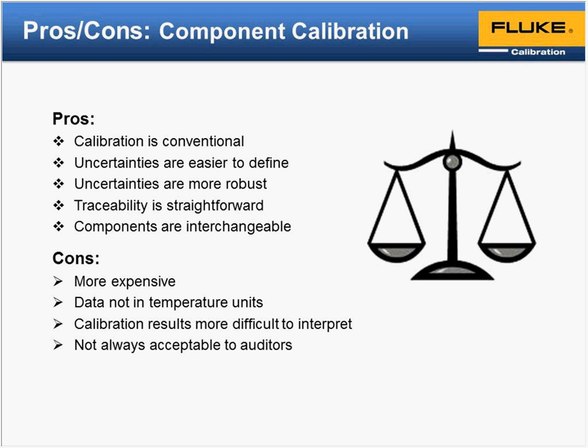So again, I'm going to touch on those really quick. Some pros and cons between the two. I've touched on them as I've been speaking. With component calibration, you're getting the best hard look at each piece. Uncertainties are, in my opinion, easy to define, and typically more robust. So you'll say, okay, we did this calibration on the probe, it went through this process comparison. The uncertainty on the comparison piece based on the reference equipment is X. And the reason we go through the calibration is comparing against typically standard resistors, making offsets to those to make sure they're reading within the specs needed. That way you've got two very versatile pieces that can be used with multiple probes and readouts. Some of the cost of that, again, you've got two calibrations. Obviously, your cost goes up a little bit.